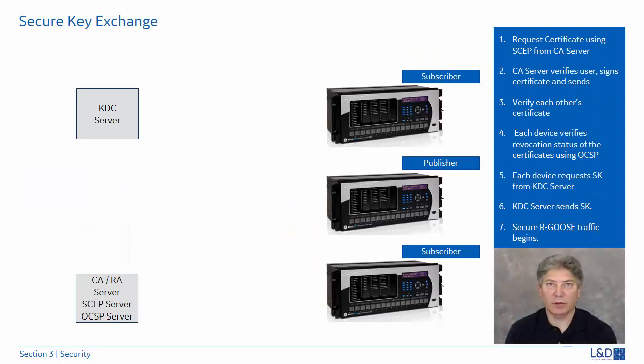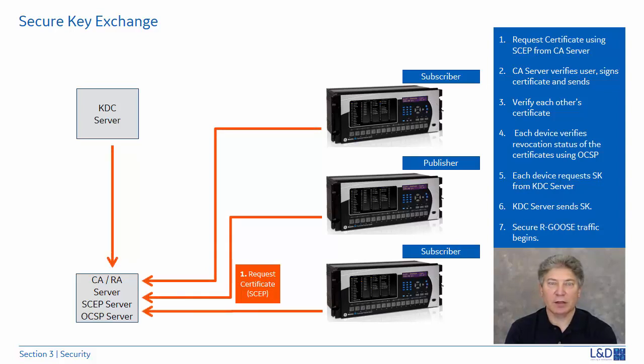Here's a simplified sequence of events to establish secure communication among routable GOOSE publishers and subscribers. There are two major exchanges going on. One is the certification, which is used to authenticate all devices exchanging keys. And two, security followed by the distribution of symmetric keys used by the publisher or subscriber for signature and encryption. So we begin with step one, and this is to provide the R-GOOSE security support for devices that is dedicated to obtaining a certificate. The devices request the X.509 certificate from the certificate authority, the CA, using the Simple Certificate Enrollment Protocol.